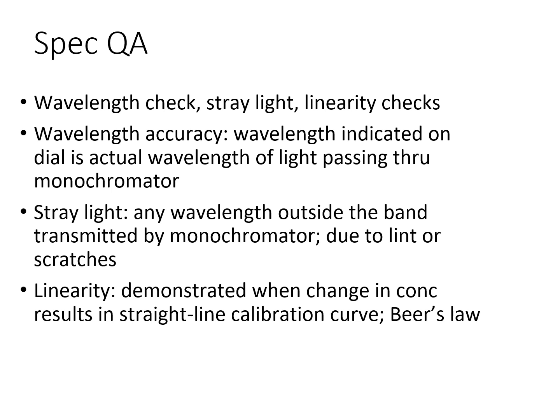Quality assurance for the spectrophotometer. So you still need to do quality assurance. It checks for the accuracy, precision, and reliability of their measurements. So the wavelength accuracy is going to be confirming the wavelength shown on the dial matches the actual wavelength that is passing through the monochromator. Errors may result in incorrect absorbance readings, and it's verified using standard solutions.